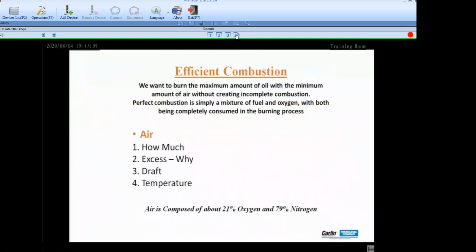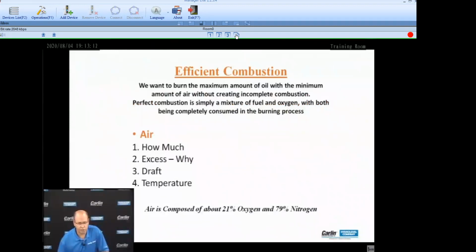So what elements are we looking for and what are we concerned with when we talk about efficient combustion? Well, how about air? Air is the one thing that we basically control. How much air? What about excess air? Why do we call it excess air? Why does it have to be excess air? The imperfect process of combustion requires that we add extra air so that we can get the oxygen content in that air for the combustion process.